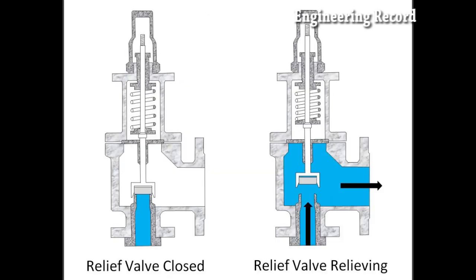Conventional type of PSV. The conventional PSV is the simplest one. This type of PSV is used whenever back pressure is relatively small and less than 10% of set pressure, or nearly zero. Due to its low immunity to back pressure, the conventional type outlet is vented to atmosphere, and mostly the fluid to be vented is non-hazardous fluid like water, air, and steam.